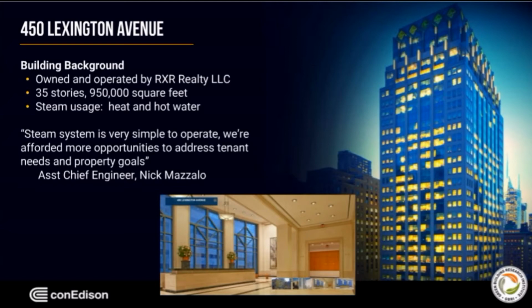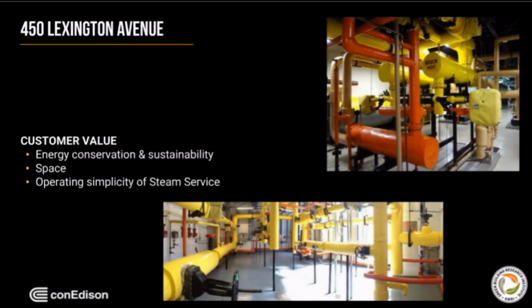Steam is used for heating and hot water. The customer's focus in choosing STEAM is energy conservation and sustainability, Energy Star score, space saving, and operating simplicity. 450 Lexington Avenue has a first-rate mechanical and steam meter room. As you can see, it is truly immaculate. Steam traps are maintained and inspected monthly. 69 traps in total are maintained and inspected every month and fully assessed once a year by a specialist contractor. This ensures that their system is safe, reliable, and energy efficient.